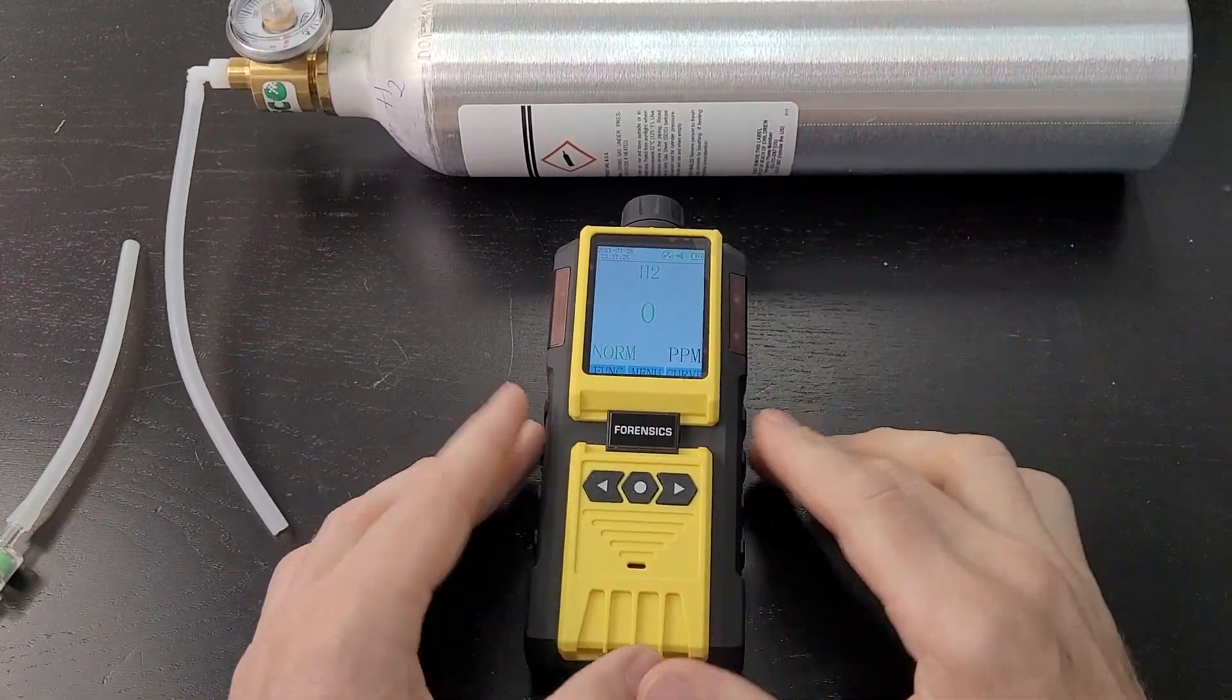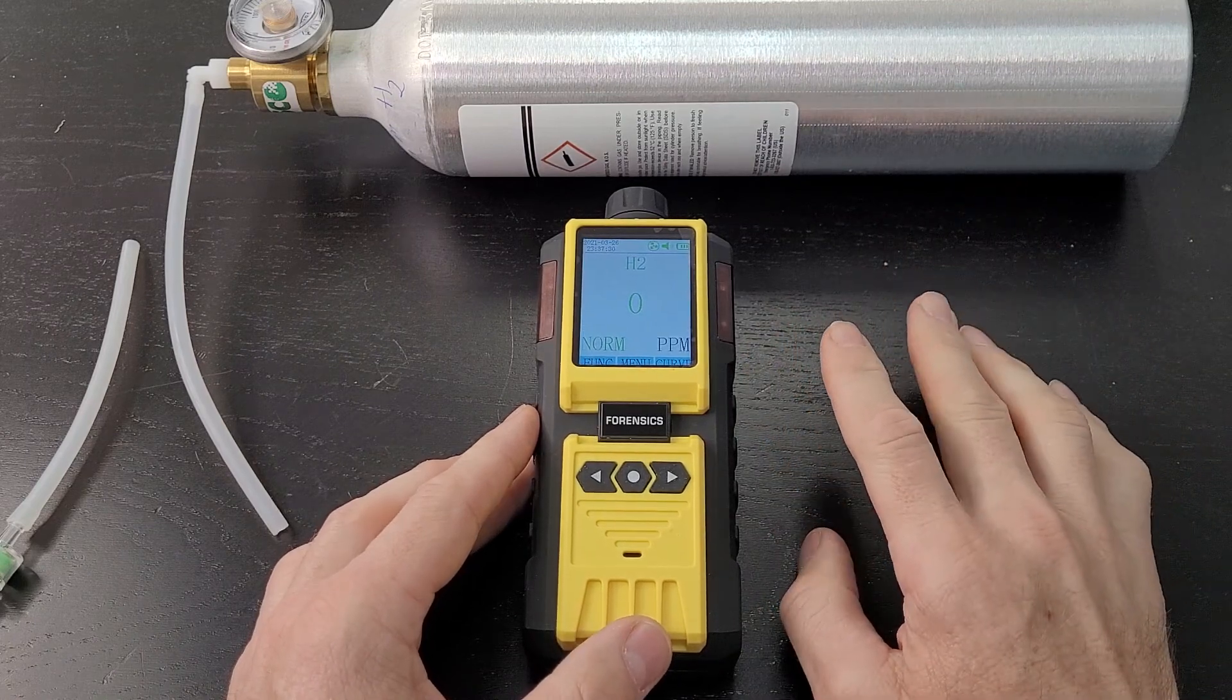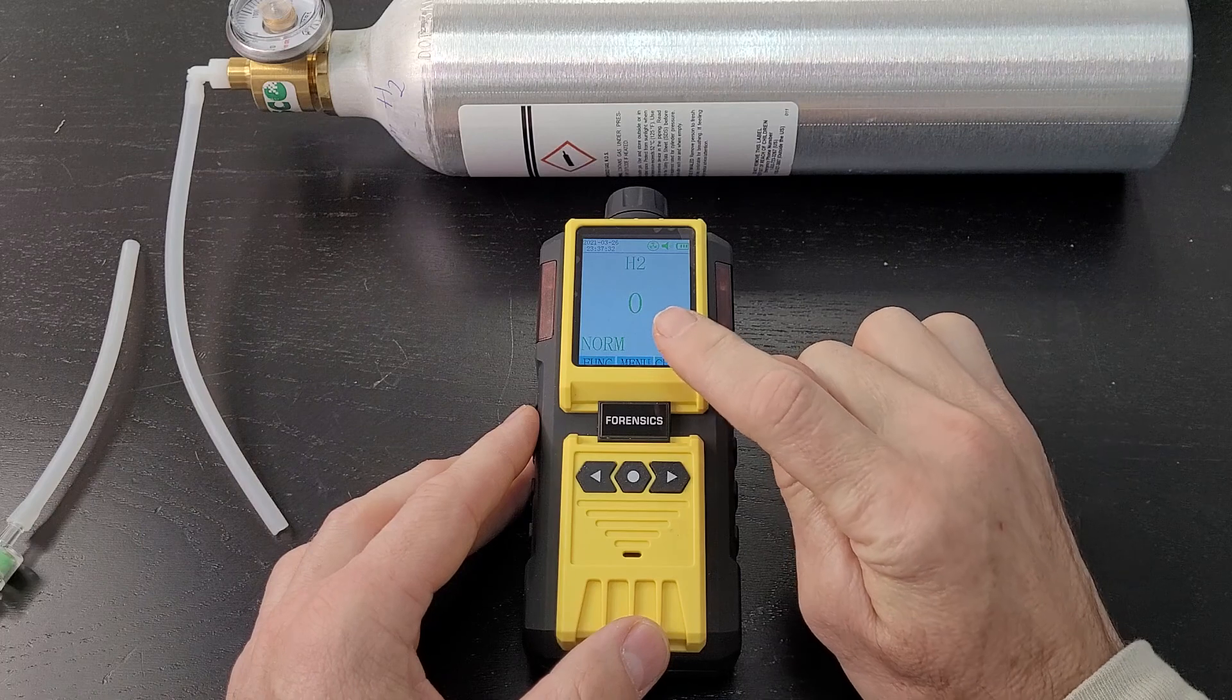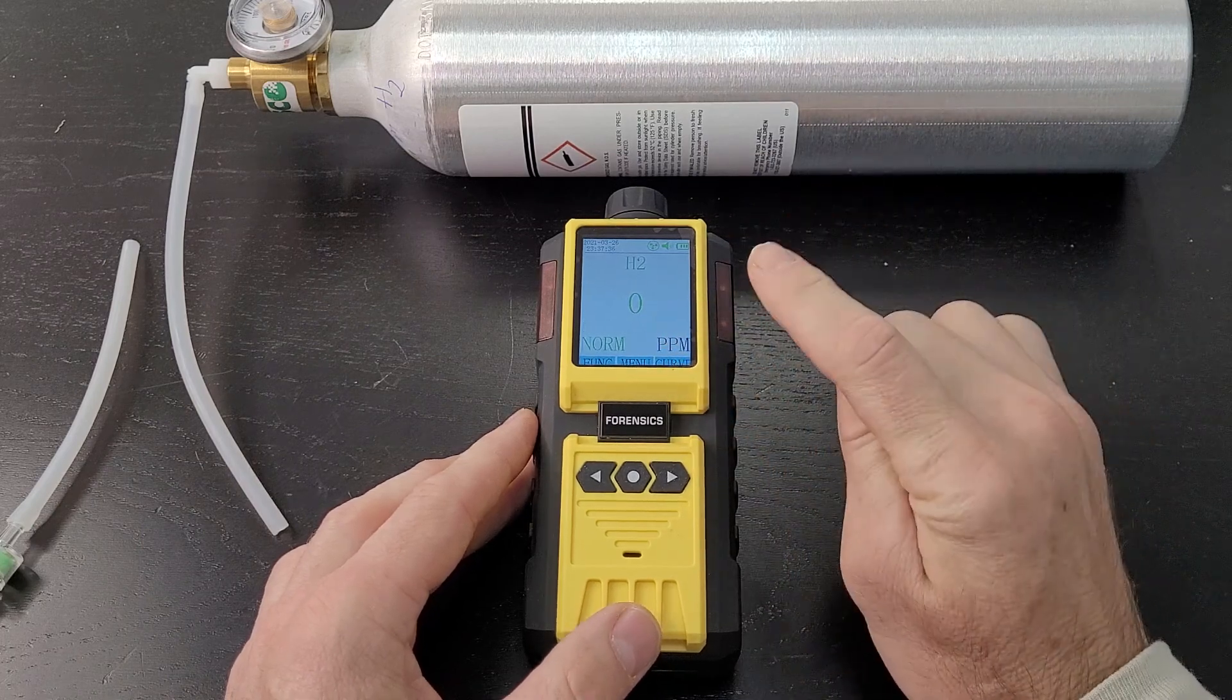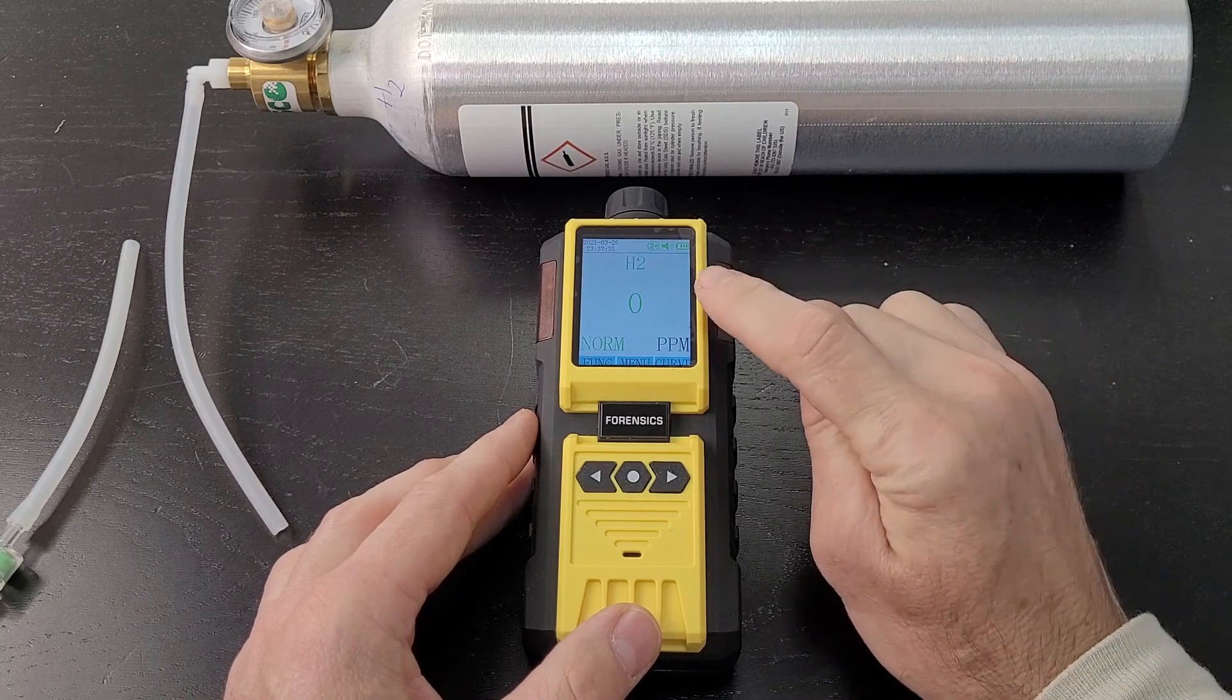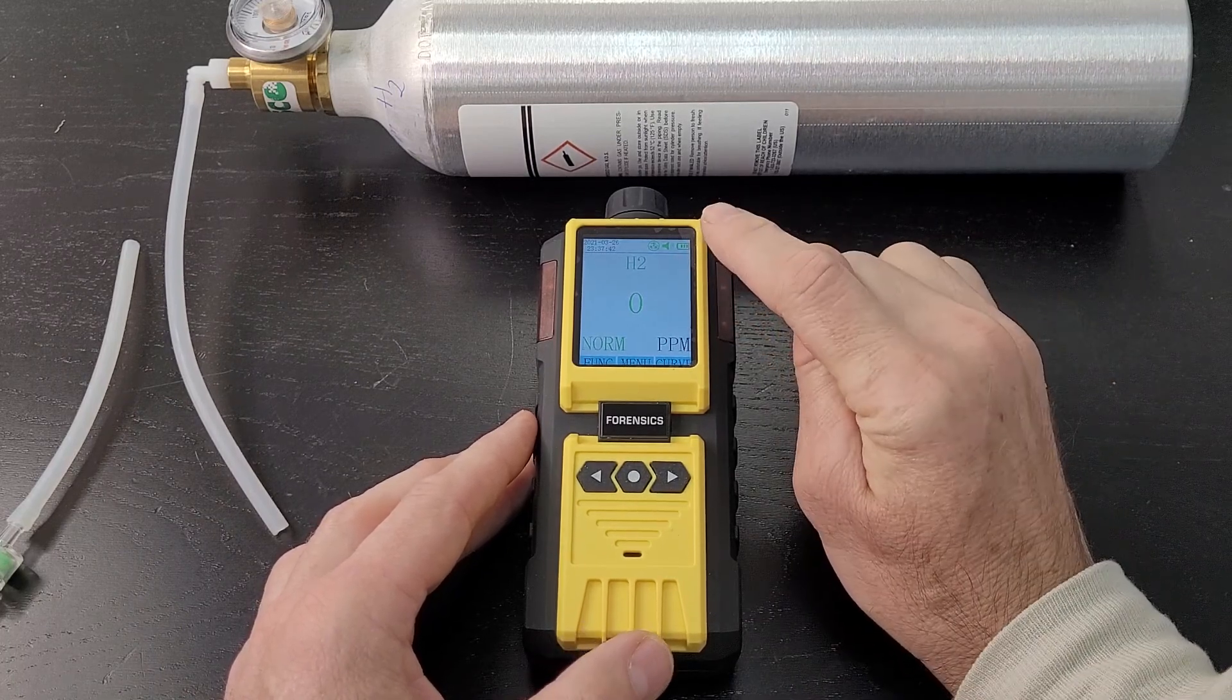Calibrating has two steps. First step is a zero calibration. We want to make sure the detector is reading zero in fresh air when it comes to gases such as hydrogen, carbon monoxide, hydrogen sulfide, and others.